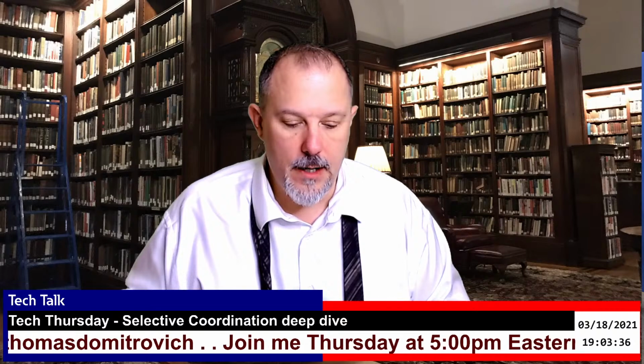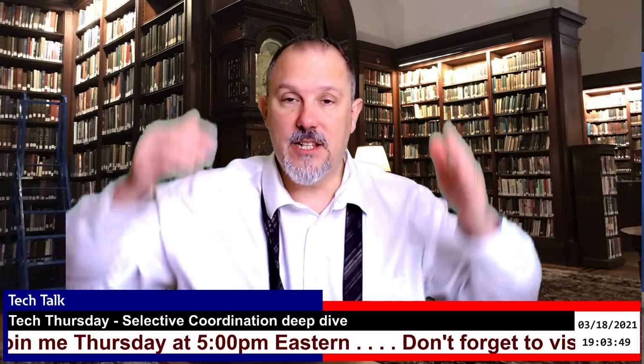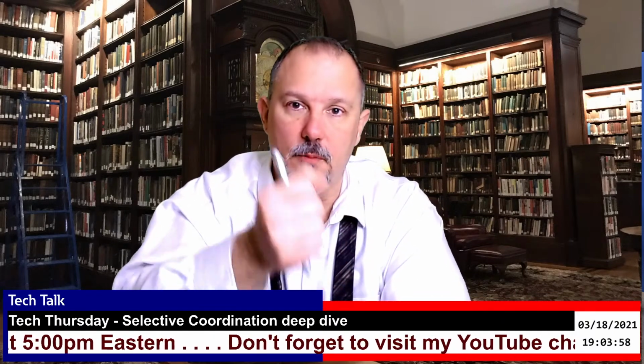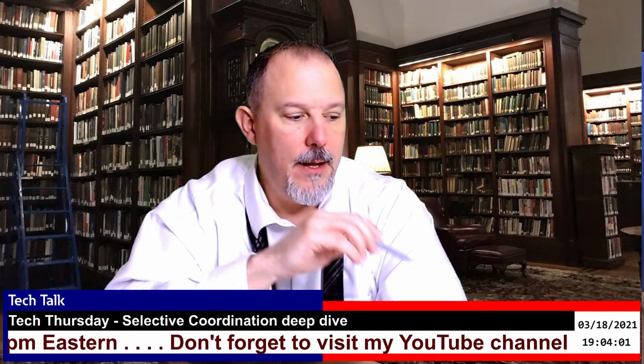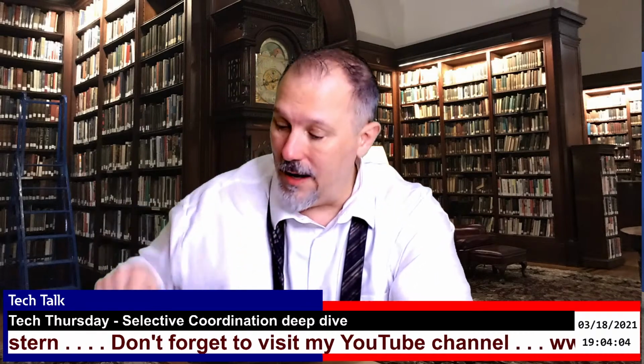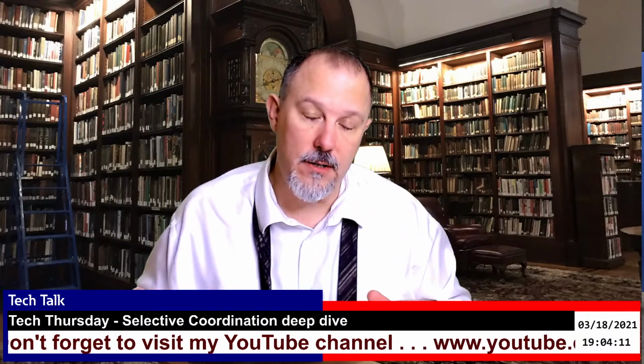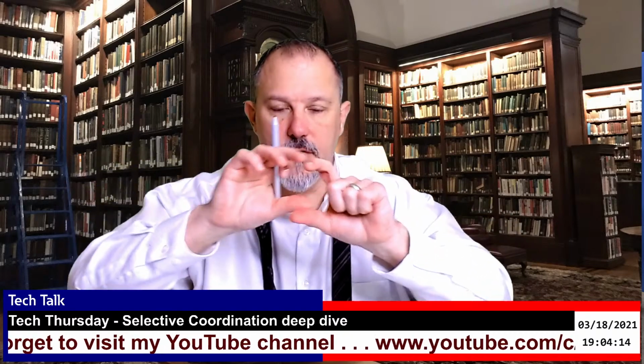It's not in any IEEE documents. It's not in any technical reference that tells you what to do. So what I've learned is when people say 0.01 seconds, they mean selective coordination because in their mind, it's all currents and all times. It's all times because people forget about current. You have to evaluate the breakers with regard to current. So 0.01 is not in the code. 0.1 is in 517, like we discussed. And that is basically ignoring fault current. And you're hiding all your curves, all of the overlaps below 0.1 seconds, and just looking at the pretty pictures and saying, do I have space?